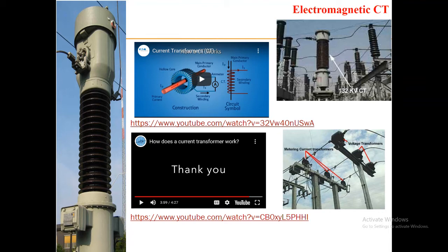Generally, when our intention is to measure high impulsive current, CTs with either air core or ferrite cores are normally preferred. Usually, CTs designed to measure high impulsive current have a toroidal core with a central hole, as you can see in the upper photograph. The toroidal core possesses one hole in which the primary or current-carrying conductor is placed, just to measure the current flowing through this current-carrying conductor. Ideally, the conductor whose current we need to measure is now acting as a primary. The core can be of split type.